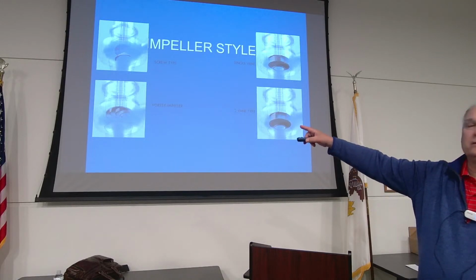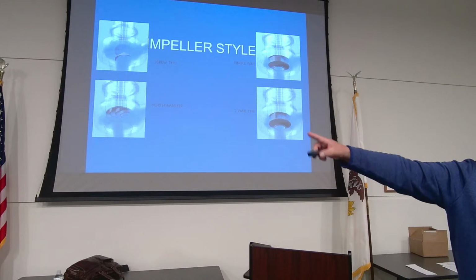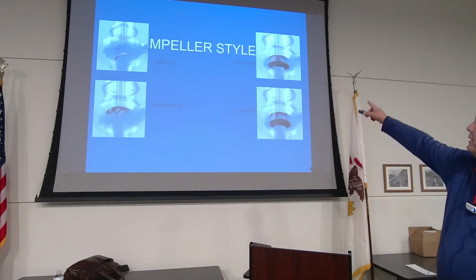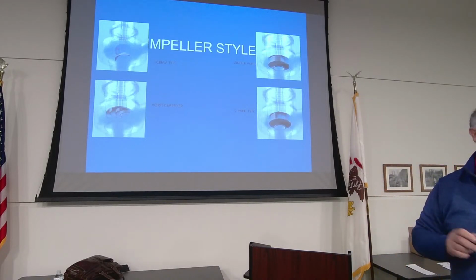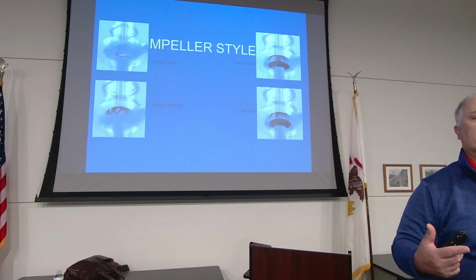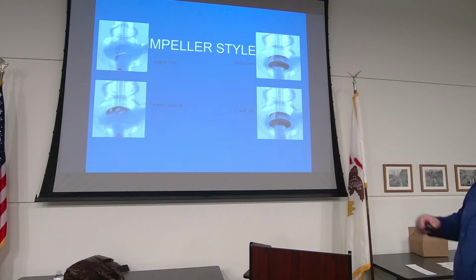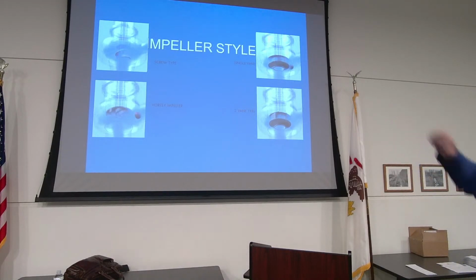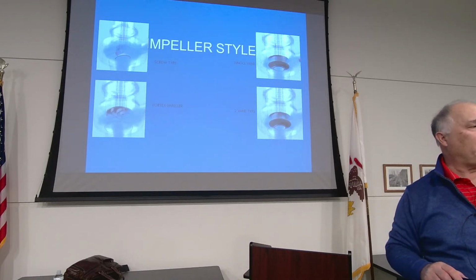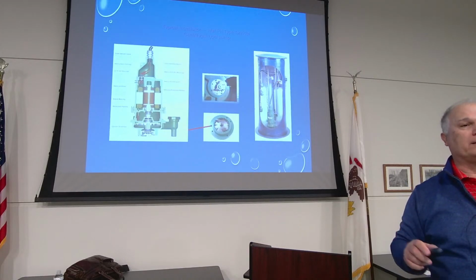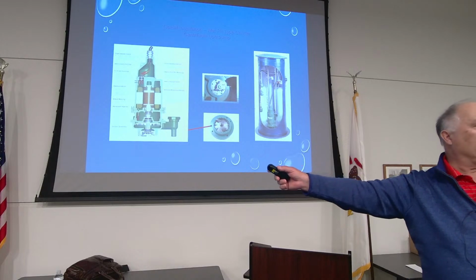All right, so with a vortex impeller pump, you can see there's nothing beneath it. There are no wear rings, there's nothing else. That just generates a big old tornado in the station. The one in the upper right is a single vane impeller pump. The single vane impeller pump will handle rags and other things. One manufacturer called it their contra block impeller. Solids come up and they get discharged by one impeller. Good impeller, good efficiency, not quite as much as the 2-vane, but there's no opportunity for a rag to come up and get stuck going out both ports like on a 2-vane.